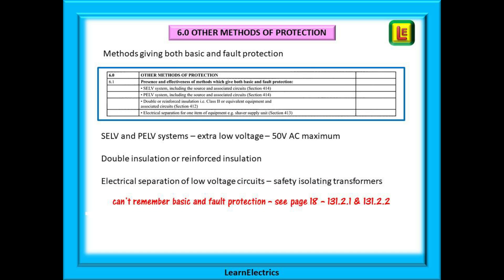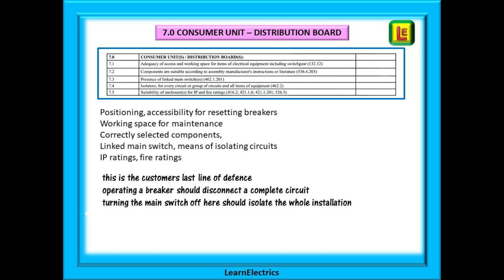Section 6 considers other methods of protecting persons and livestock — methods such as SELV or PELV systems. These are extra-low voltage (ELV), up to 50 volts AC maximum. Then there is double insulation or reinforced insulation around the copper conductors, and we may have electrical separation of low voltage circuits using safety isolating transformers. Low voltage (LV) circuits are between 50 volts and 1000 volts AC with reference to earth. An example of electrical separation using a safety isolating transformer would be an electric shaver socket to the approved BS EN standards — 230 volts in and 230 volts out, but the output is separated from earth.